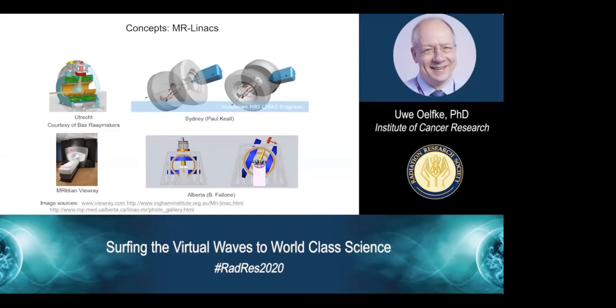A similar concept with the split magnet and cobalt sources, but also with the MR Linac, with a conventional Linac, is realized by ViewRay, the MRIdian system, and then an interesting experimental approach where actually the magnet and the Linac simultaneously rotate around the patient, as is indicated here. It's also a split magnet, as you can see, and the beam can be either inline or parallel with the magnetic field lines or perpendicular to the magnetic field lines.